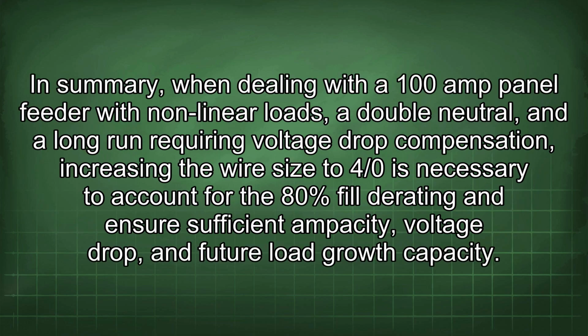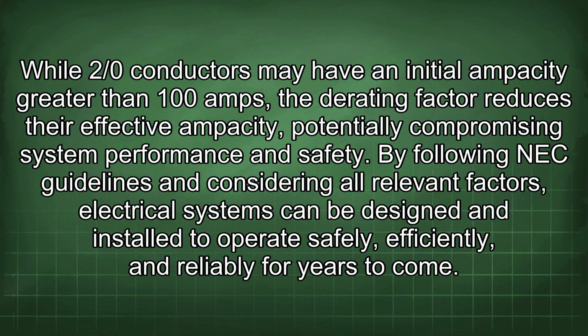In summary, when dealing with a 100 amp panel feeder with nonlinear loads, a double neutral, and a long run requiring voltage drop compensation, increasing the wire size to 4/0 is necessary to account for the 80% fill derating and ensure sufficient ampacity, voltage drop, and future load growth capacity. While 2/0 conductors may have an initial ampacity greater than 100 amps, the derating factor reduces their effective ampacity, potentially compromising system performance and safety. By following NEC guidelines and considering all relevant factors, electrical systems can be designed and installed to operate safely, efficiently, and reliably for years to come.